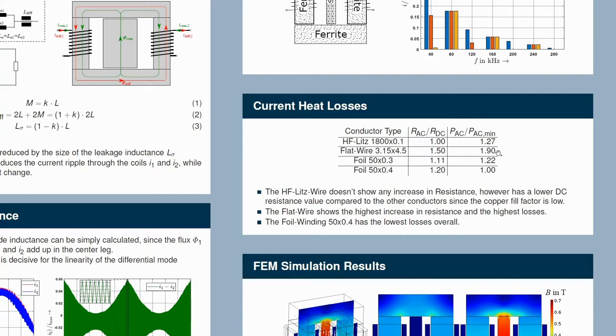The foil conductors have medium skin proximity losses, but they have a lower DC resistance value compared to the high frequency Litz wire, since the copper fill factor is lower for the high frequency Litz wire.